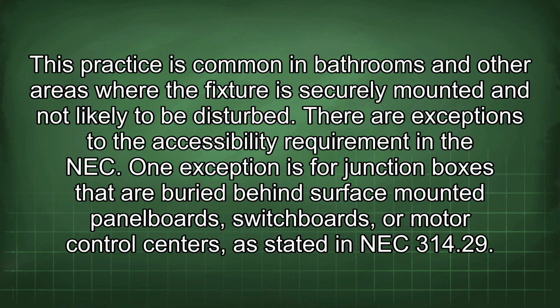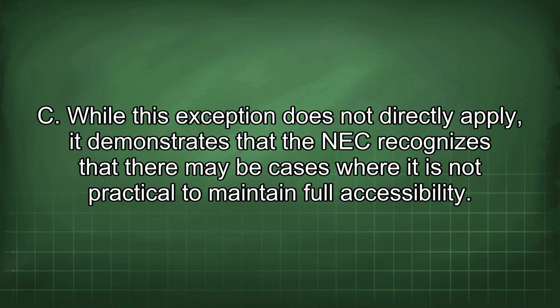One exception is for junction boxes that are buried behind surface-mounted panel boards, switchboards, or motor control centers, as stated in NEC 314.29. While this exception does not directly apply, it demonstrates that the NEC recognizes there may be cases where it is not practical to maintain full accessibility.